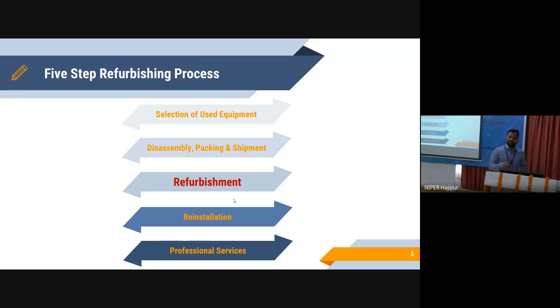Now the refurbished product has arrived at the user site, and the party who has performed the refurbishment has to follow the same installation procedure as mentioned by the original equipment manufacturer. They have to reinstall the device at the use site. They have to show that the device is performing optimally, as compared to when it was new, in front of the user, and they have to hand over documents showing that they have followed good refurbishment practices. A compliance certificate they have to submit to the user.